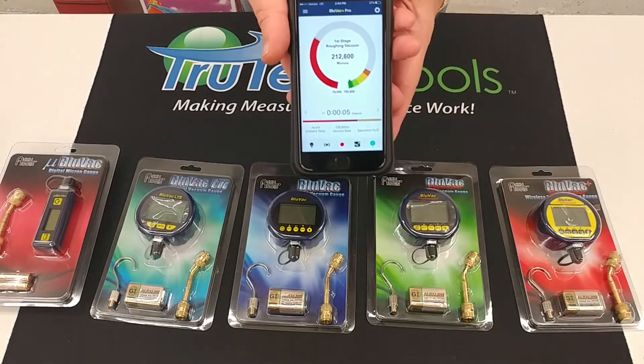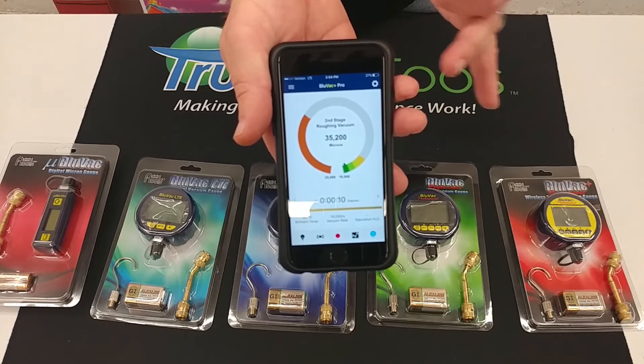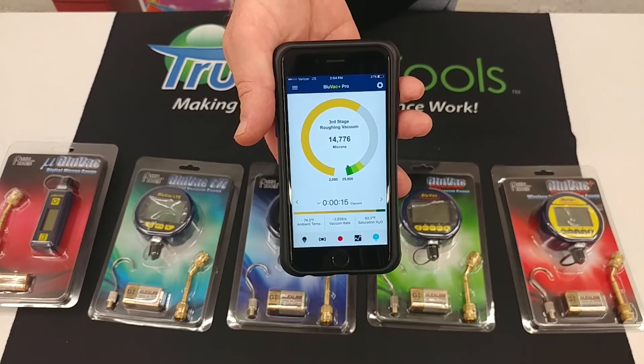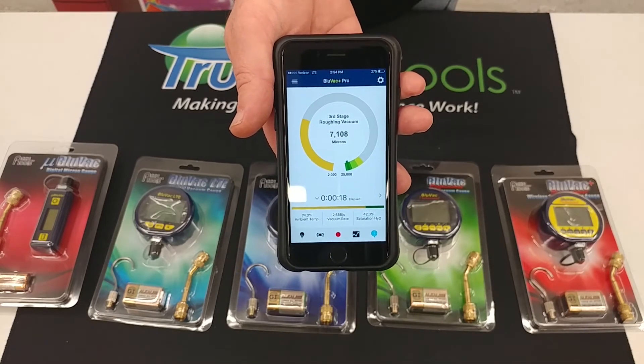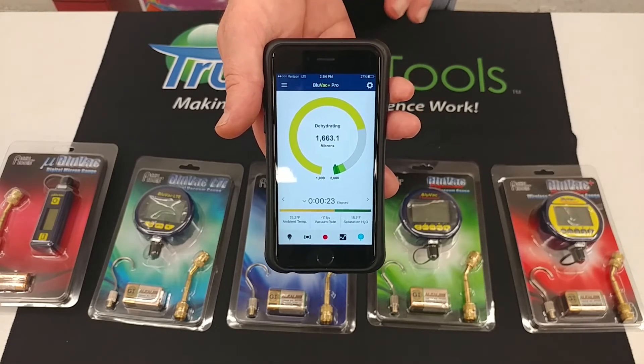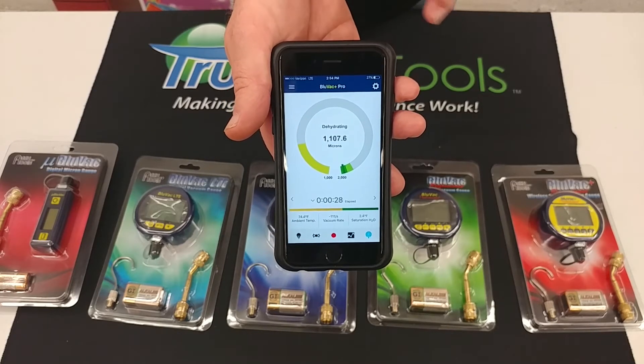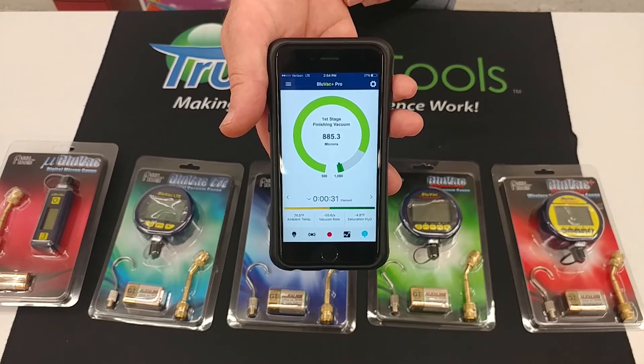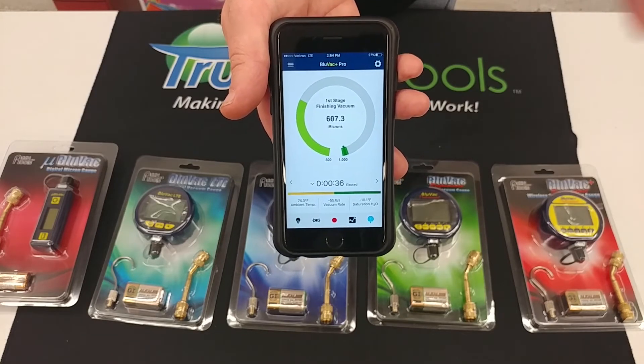Here's a quick screenshot of the app. There are three different apps that work with the Professional Plus. First is the Bluvac app itself, which documents everything — your pulldown, your leak rate indication, and confirmation that you did a good evacuation, which is important for companies that need to document the evacuation was done properly. You can save this to a full report. It also works with MeasureQuick, developed by Jim Bergman, which includes geotagging and full reporting. It also works with the iManifold.